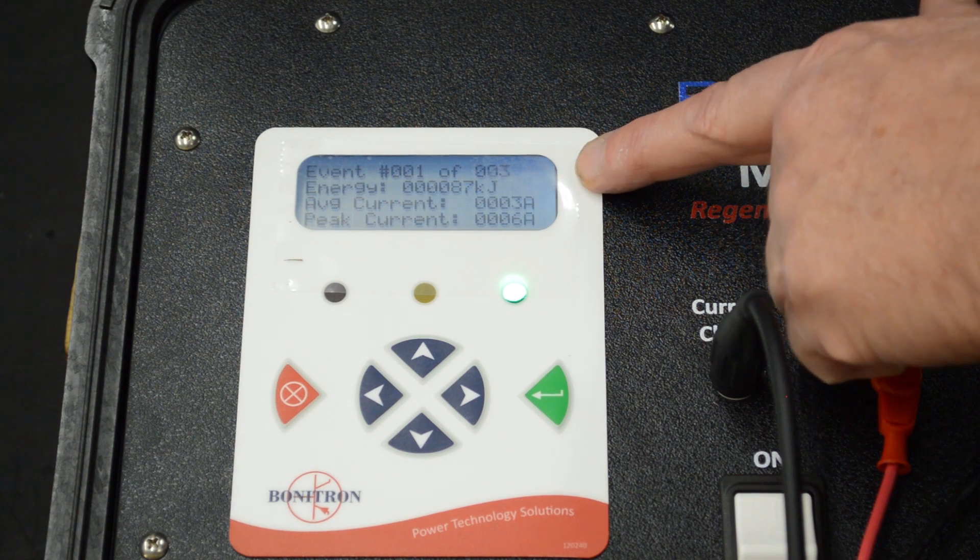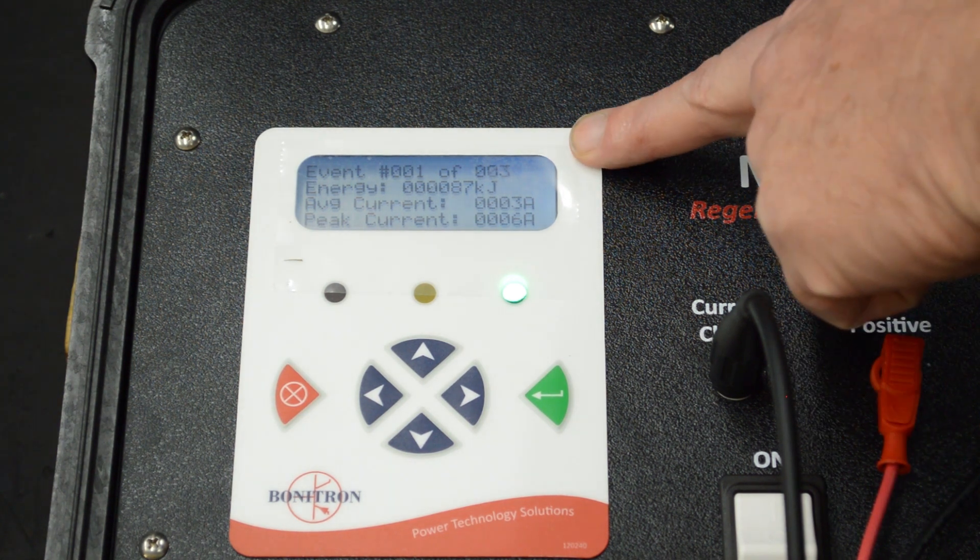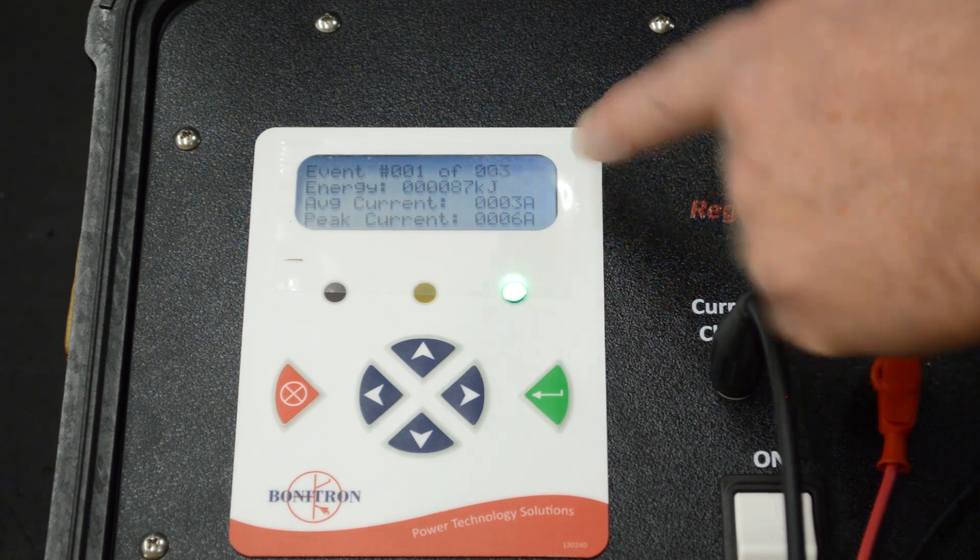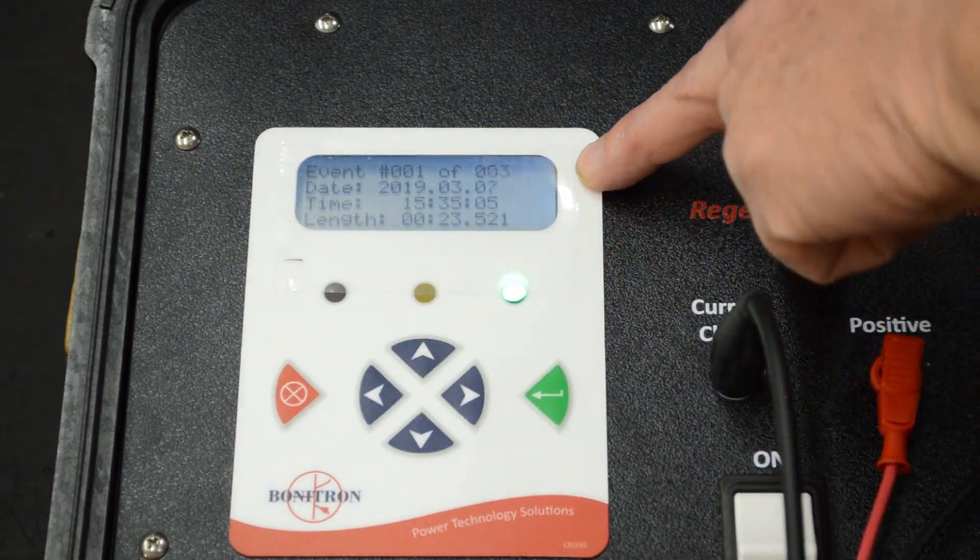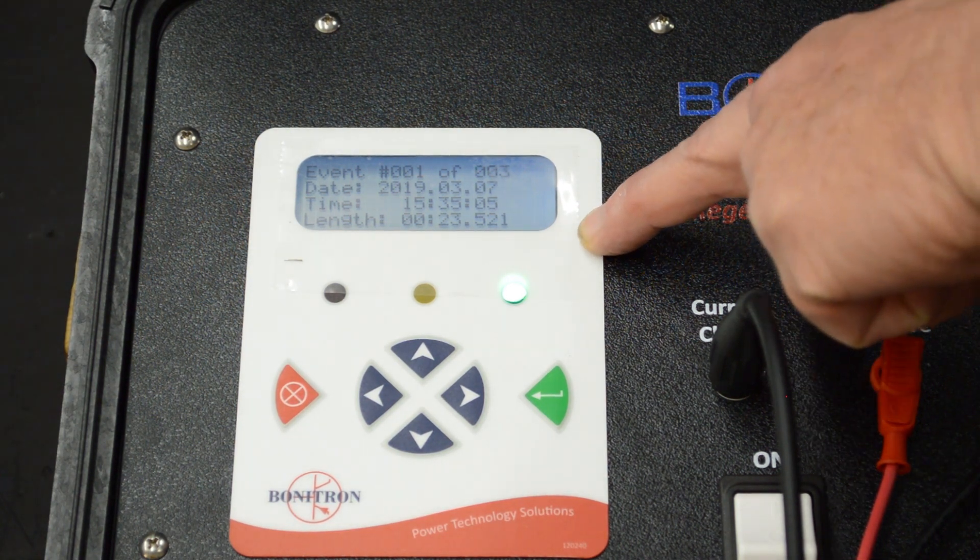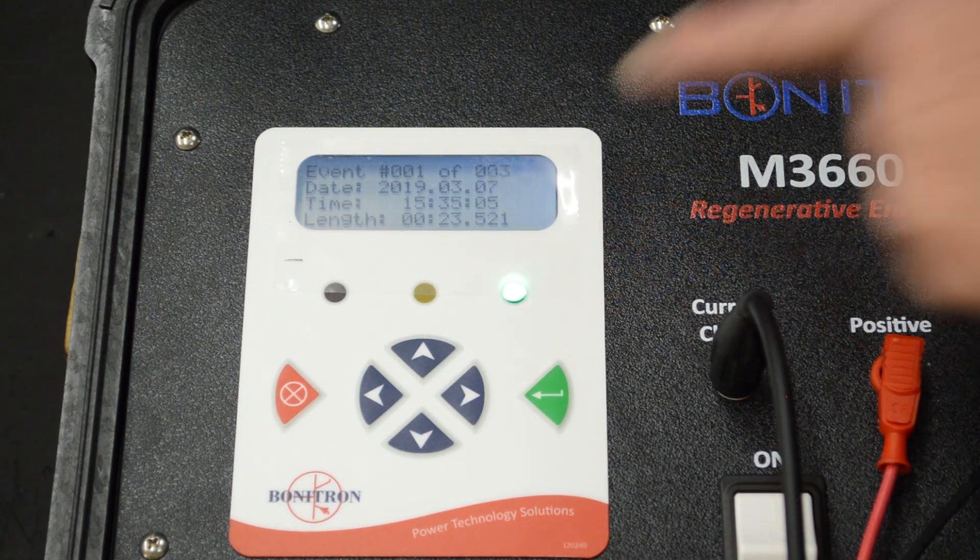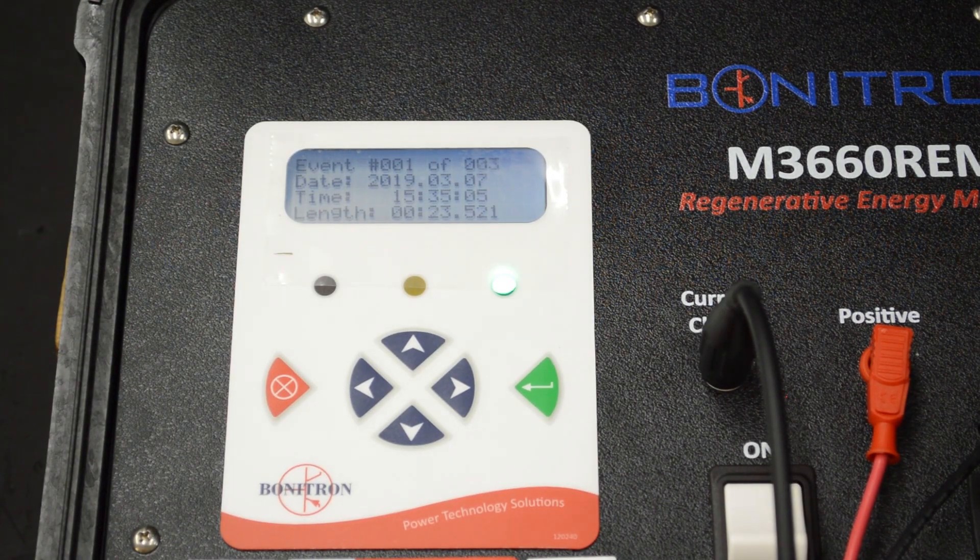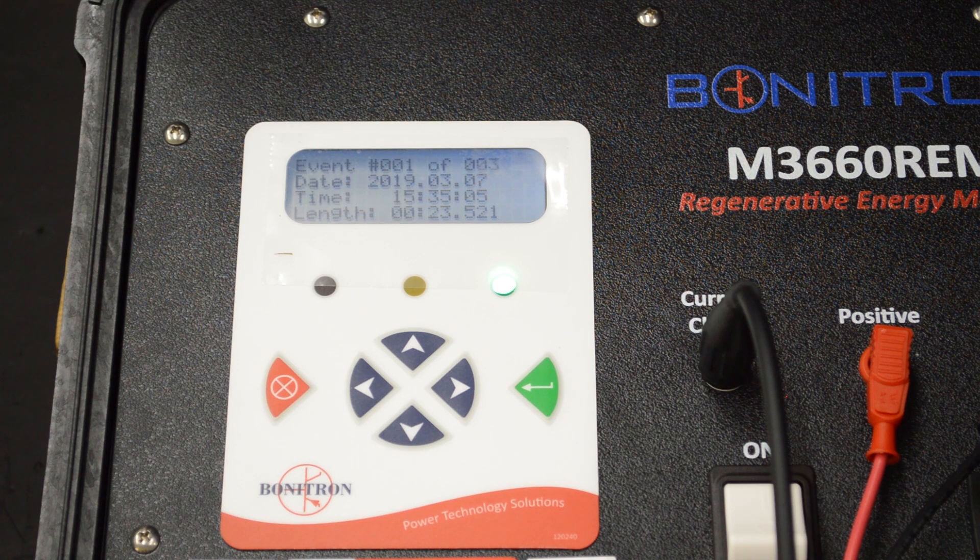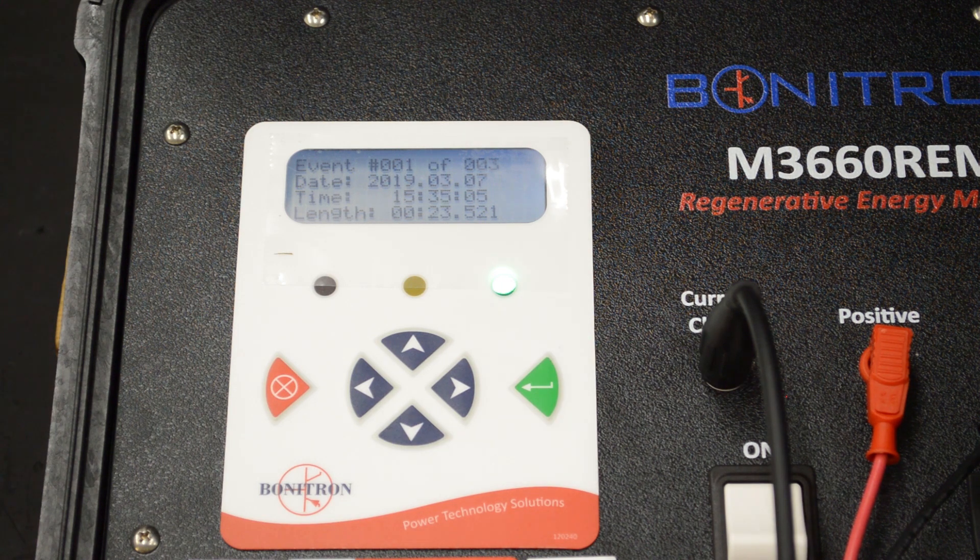Shows you the energy in kilojoules. It has a regen event number, average current, peak current. Gives you the date of the event, the time, and the length of the actual regen energy event. So what you can do is you can take this information and you can determine if your braking solution is adequate, or if possibly you need more dynamic braking, or you could use a line regen for your regen profile.